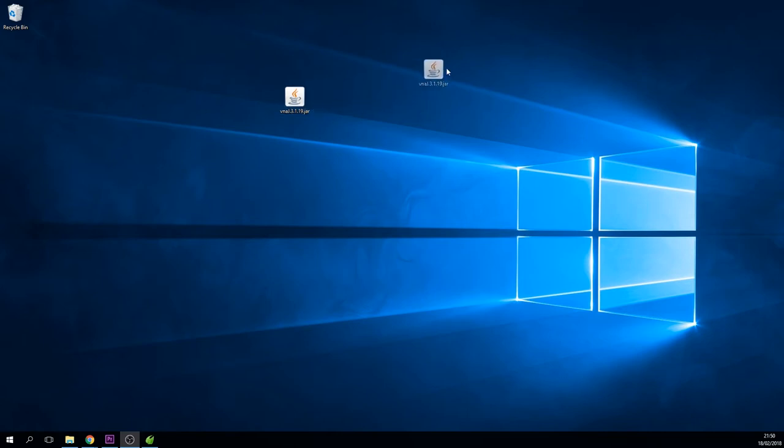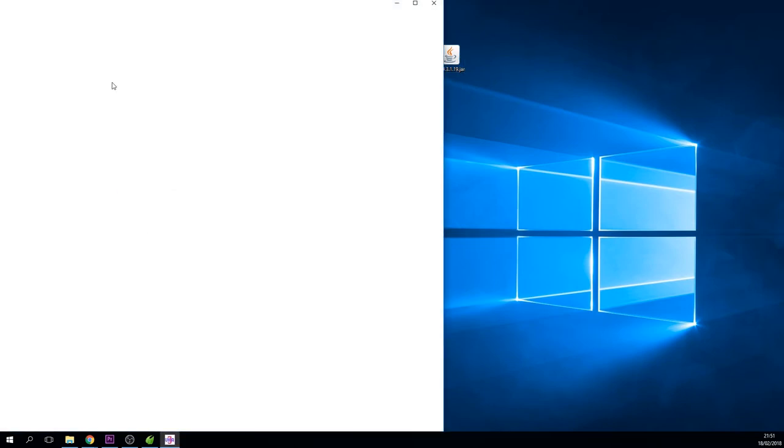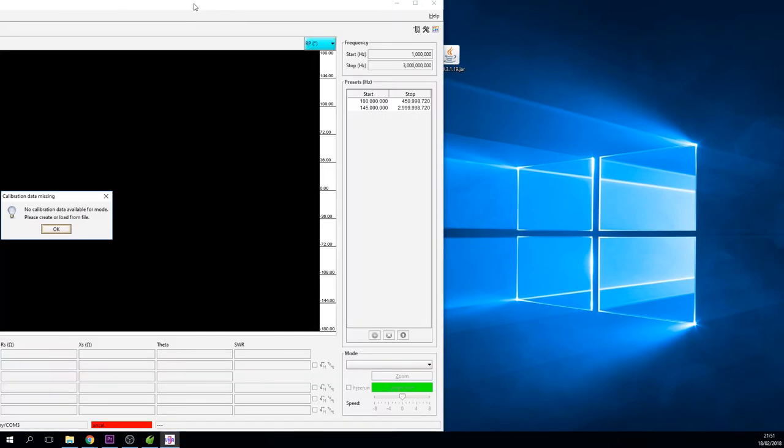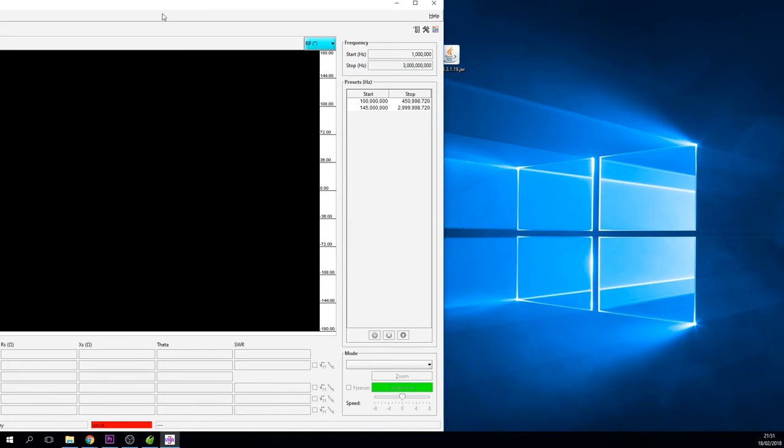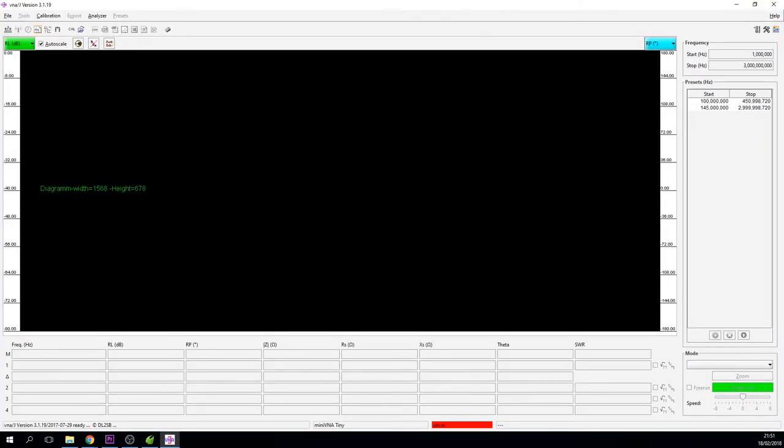Once you've done that, the self-executable Java file will sit on your desktop. I've just plugged in my VNA Tiny, you don't need any Windows drivers, it's all fairly self-explanatory. Once this installs it will associate it with a COM port, in my case it's COM3, and you're just going to run the file. The first thing it's going to do is grumble that there's no calibration data. Just say okay and we're going to now have to create some calibration data.